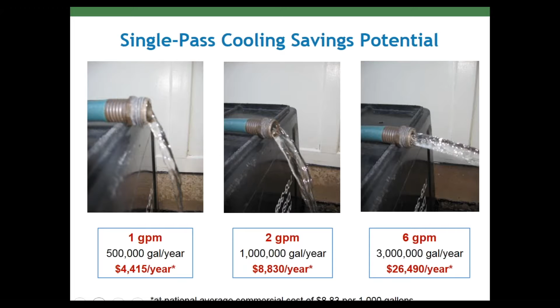On the left, where the flow appears to be not much more than a trickle, if this is happening, this would consume about 500,000 gallons of water per year and cost about $4,000 at average water and sewer rates. Once we get to the far right, you see the flow equivalent to a garden hose at full flow. If that's going 24/7, it would be 3 million gallons of water per year and over $26,000 in water savings.